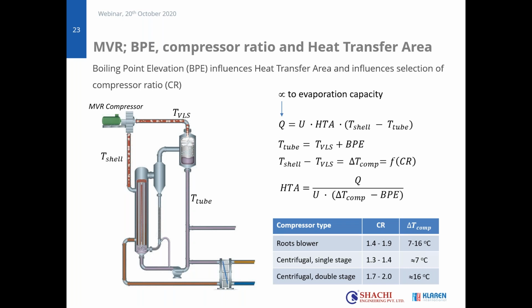So if we combine that, then the heat transfer area that I need will be the heat duty, but that's simply the capacity of the system, divided by the heat transfer coefficient, and divided by the difference between the temperature rise of the compressor minus the boiling point elevation. So already to give you one idea, suppose that my delta T over the compressor is 6 degrees and my boiling point elevation is 6 degrees, there is no driving force for the heat exchanger and the system cannot work. So this is already how important this is.